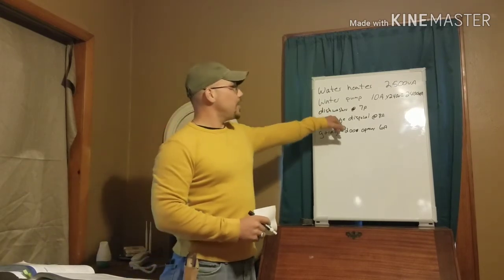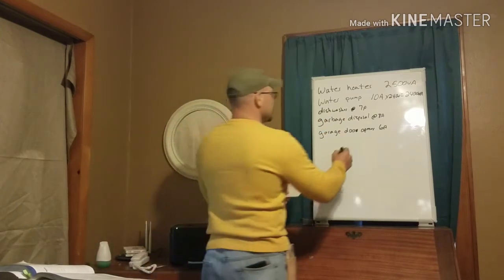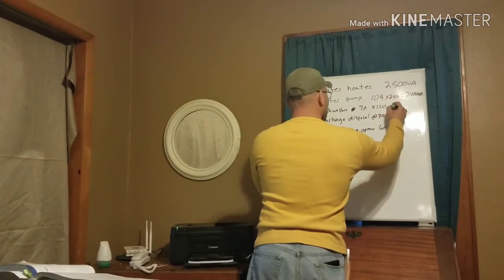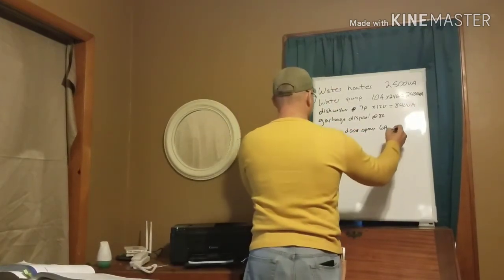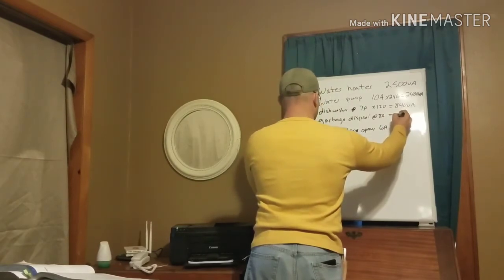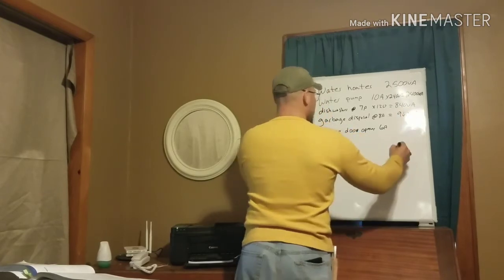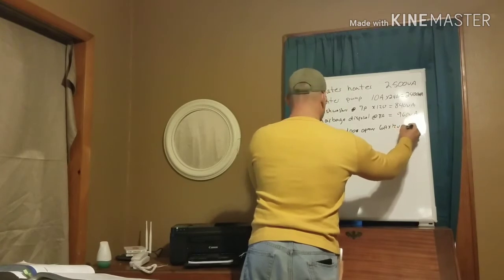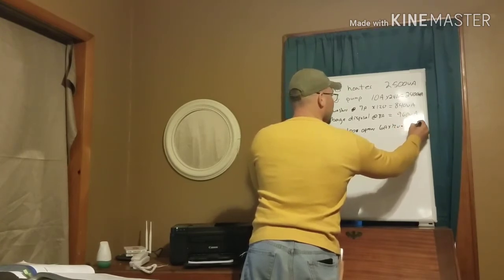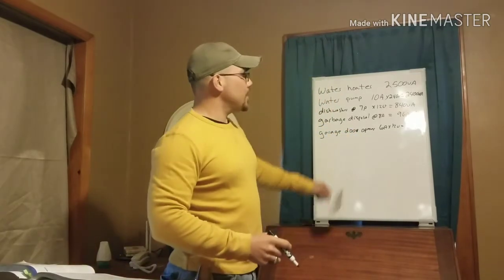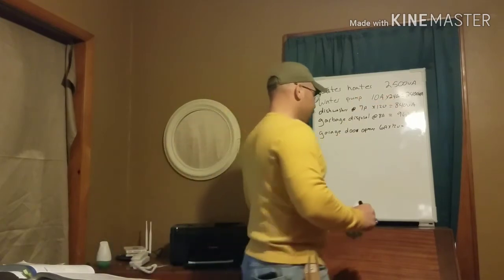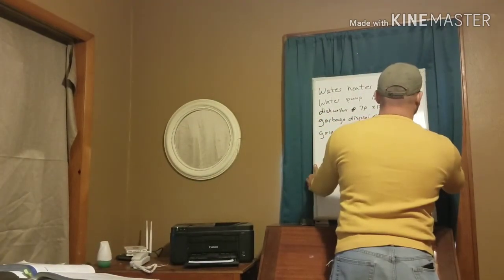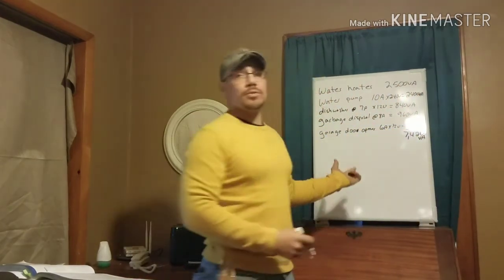Those last three — dishwasher, garbage disposal, and garage door opener — are all 120-volt appliances, so it's important to know the voltage each appliance takes. Multiplying each by 120 volts: 7 amps × 120 = 840 VA; 8 amps × 120 = 960 VA; 6 amps × 120 = 720 VA. Once we convert all fastened-in-place appliances to VAs we can add them up, giving us a total of 7,420 VA.